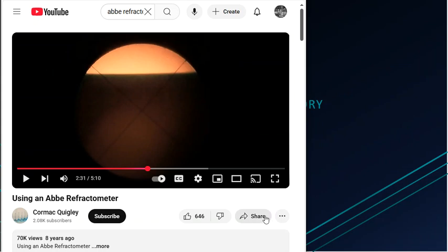Like I said, most of the time when you put a sample onto the instrument, you are not going to hit this division line smack dab in the middle. So there's the crosshairs, and it's going to be our job to lower this black half down to the crosshairs. So that's going to be the main adjustment knob that we're going to have to deal with first. That raises and lowers this dark half to make sure that we have it at an appropriate level. So this person's going to have to take that main adjustment knob and lower this black area down until it gets to the crosshairs. That way the top half is light and the bottom half is dark.